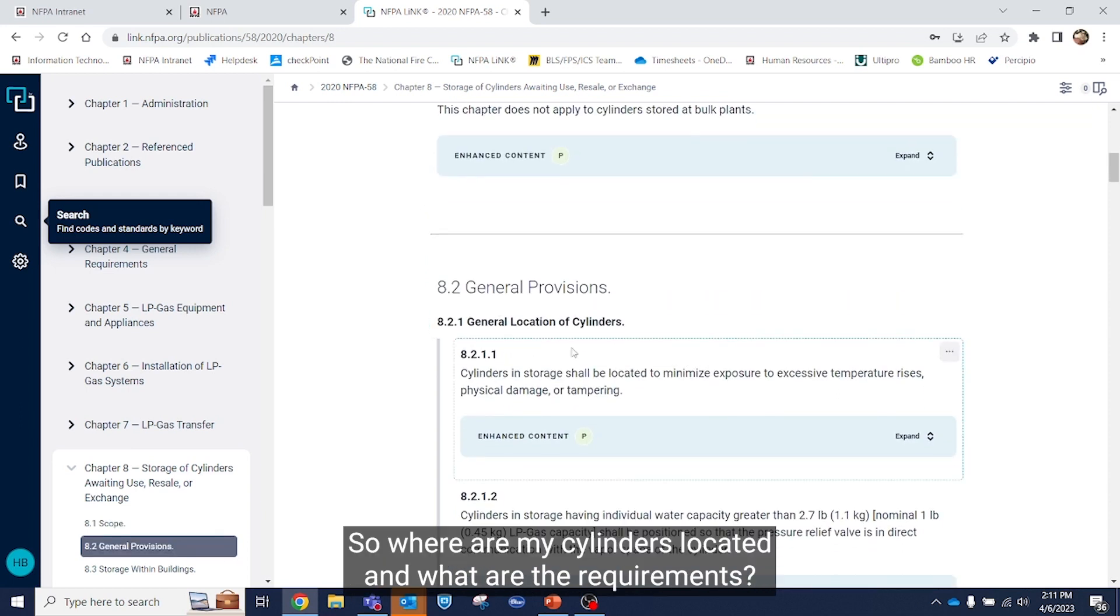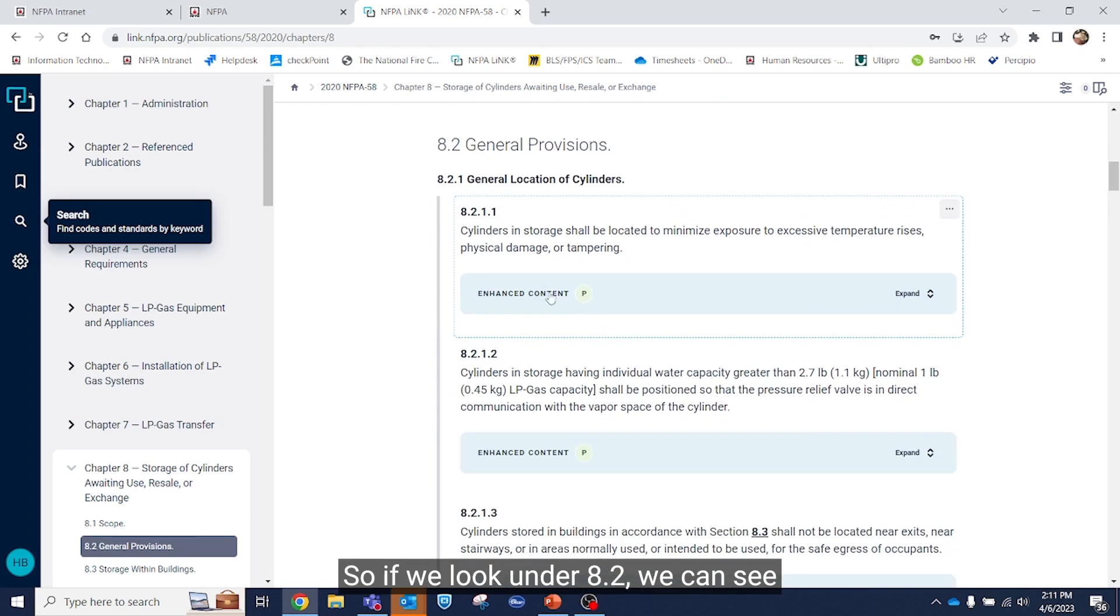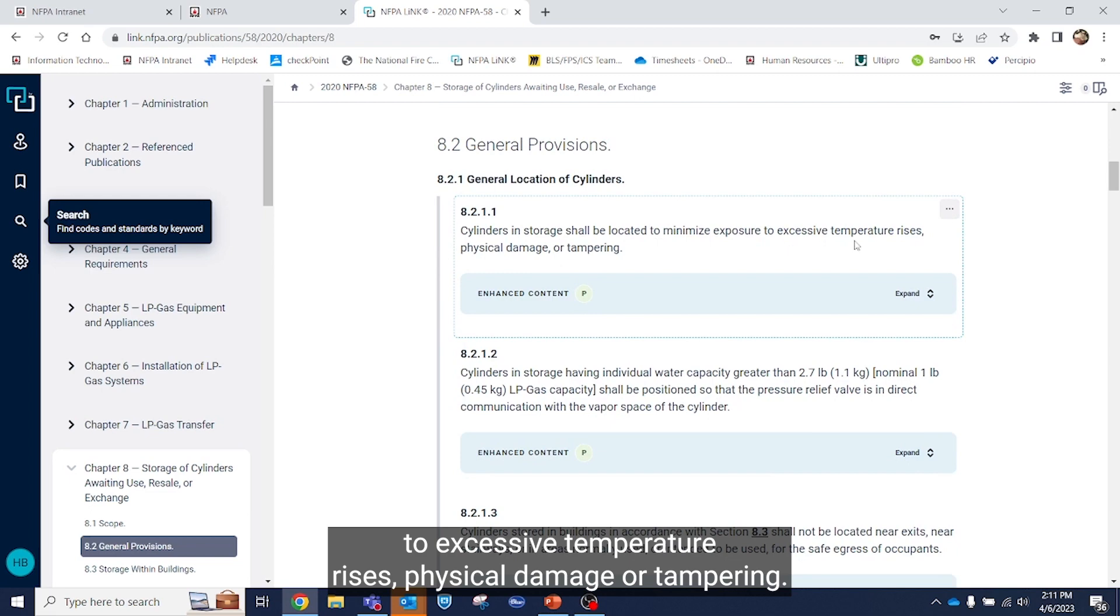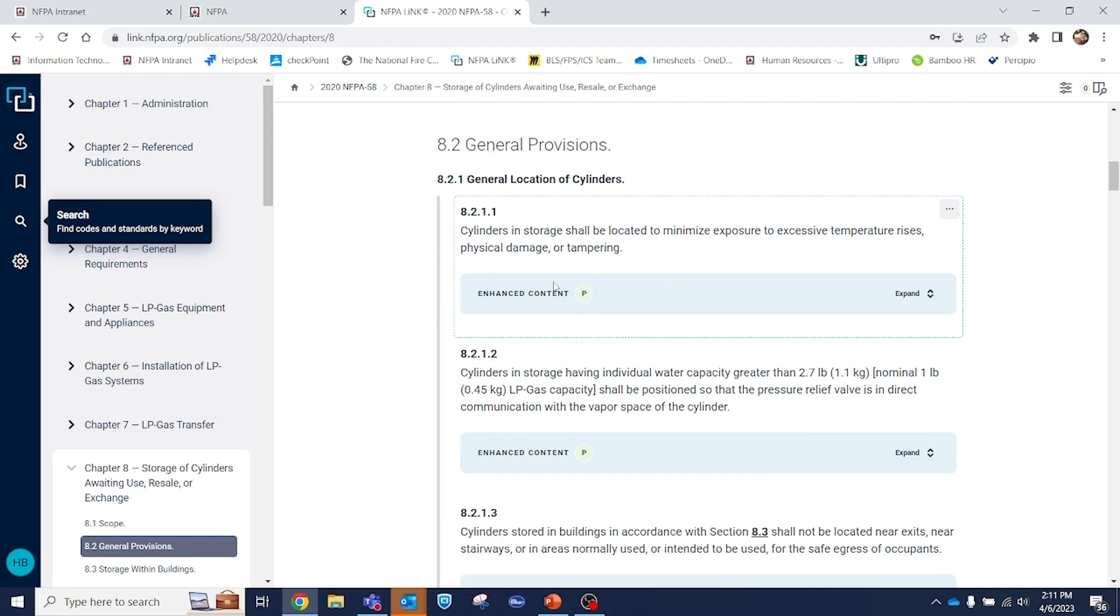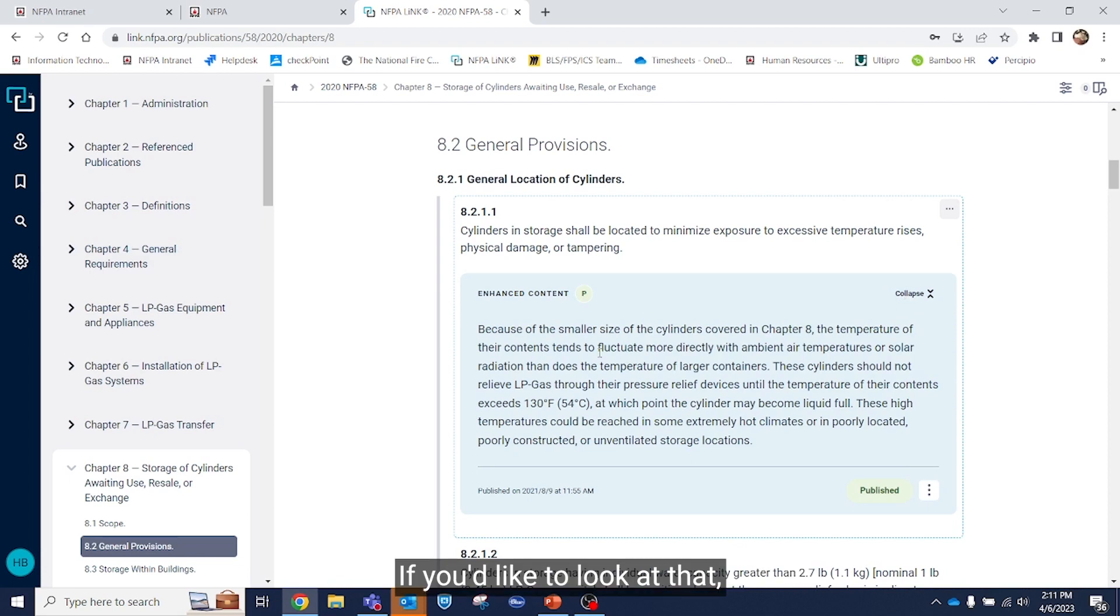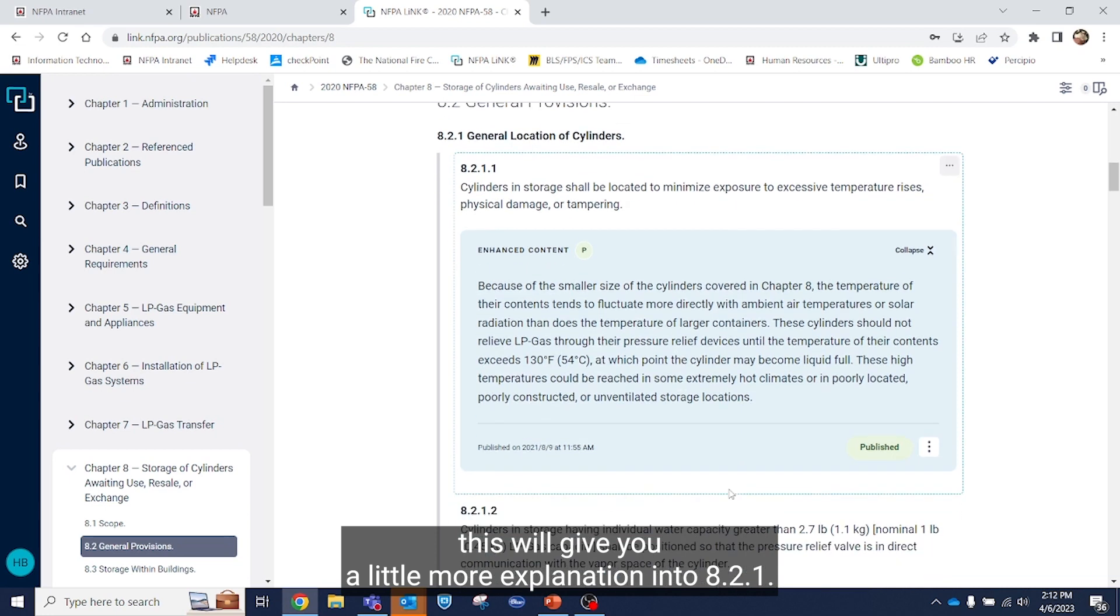So where are my cylinders located and what are the requirements? If we look under 8.2, we can see cylinders in storage may be located to minimize exposure to excessive temperature rises, physical damage, or tampering. You also have enhanced content here if you'd like to look at that. This will give you a little more explanation into 8.2.1.